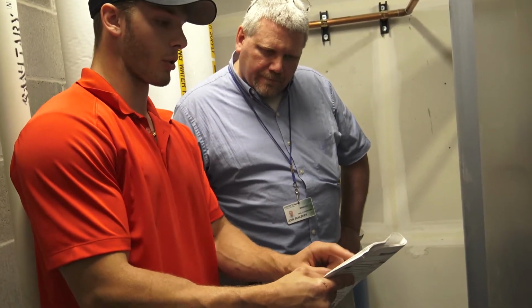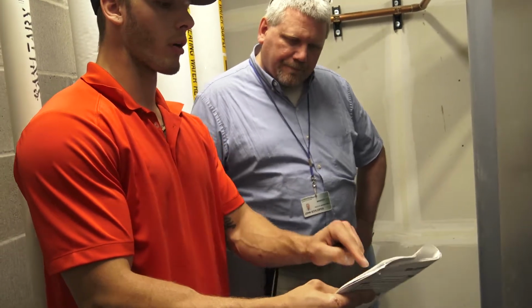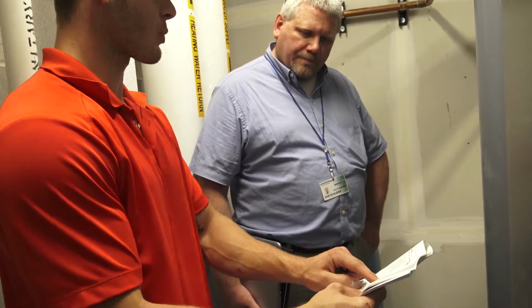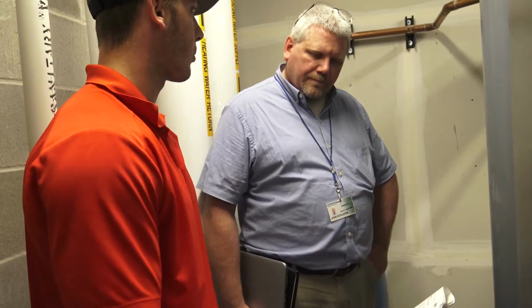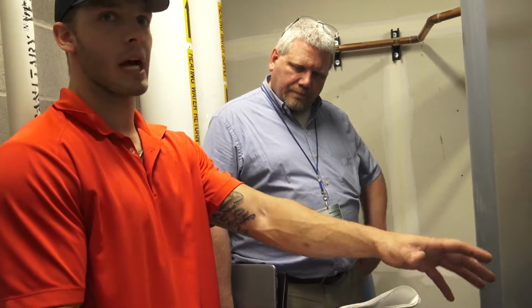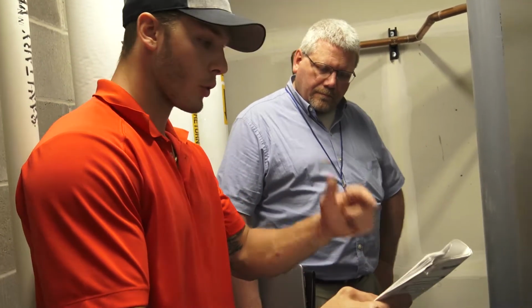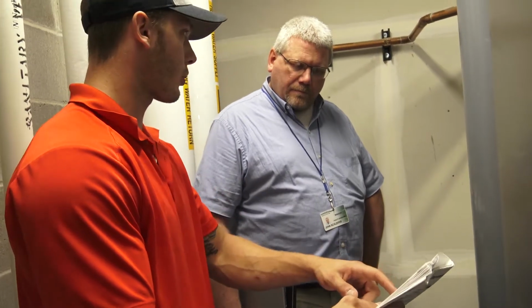These are your CO2 numbers and these are your O2 numbers. Gotcha. You want to really match CO2. That's what you want to try to stick to. Your oxygen levels are going to fluctuate a little bit more. Sure. And it tells you propane, it tells you how to turn it. They have arrows on the gas valve adjustments for that, but it'll even tell you to increase CO2, turn it a quarter turn counterclockwise. So it's spelled out in there.